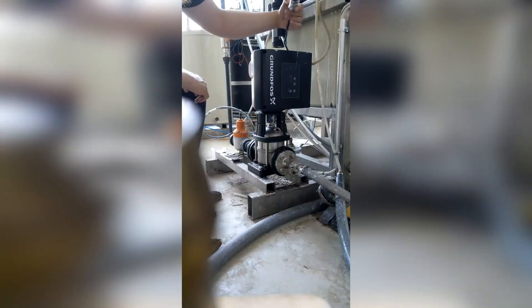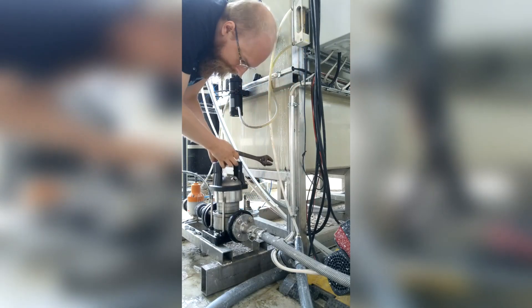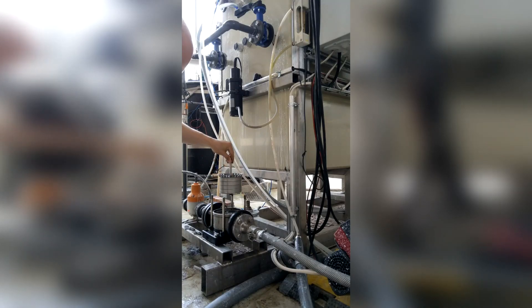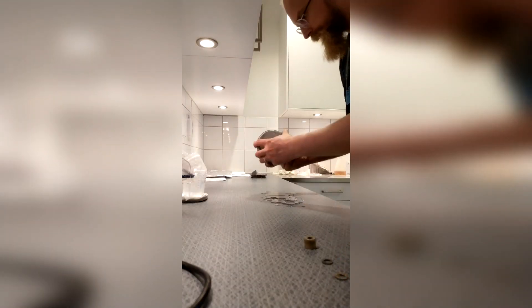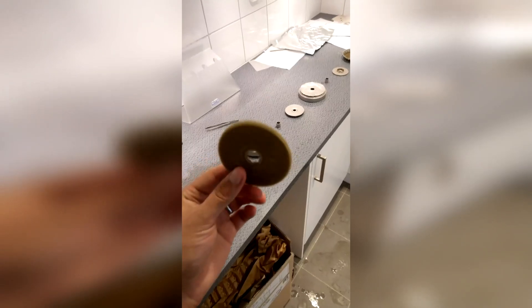This pump is the most difficult part of the process — it is literally in pain. So here is me disassembling the pump. First we detach the pressure sensor from here. This is a bit of an issue: as you can see, this is covered with something solid on the inside as well. If you compare this one to this one — this is what it is supposed to look like — but there is still some stuff inside.